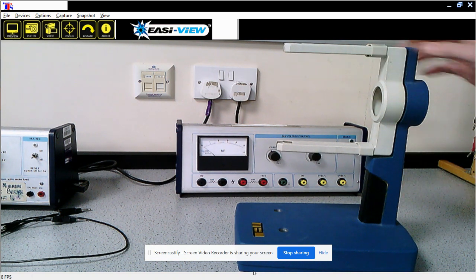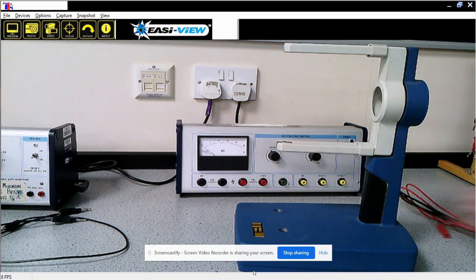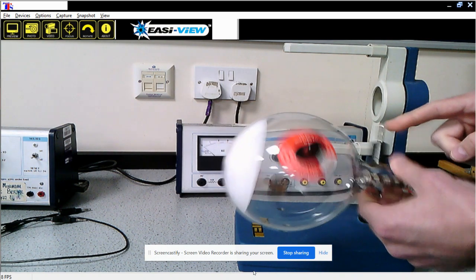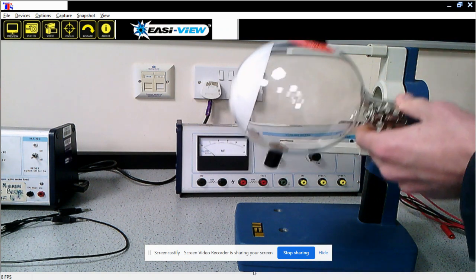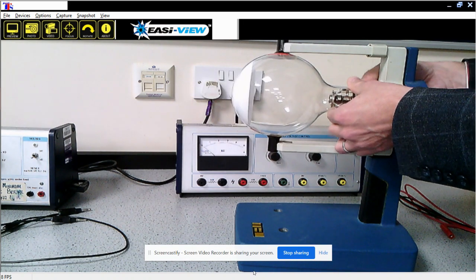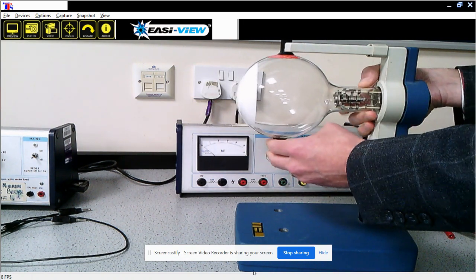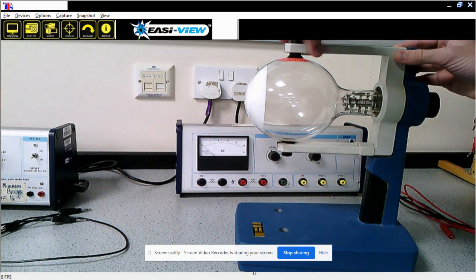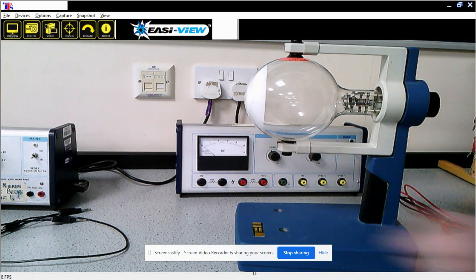When I'm putting the tube in, I'm going to check that these sliding plastic sections are slid to the right, because they will tighten up and grip the beam tube as you move them to the left. So I'm going to have this set up so that this connection is pointing away from me, because that's going to be the anode and that's going to be at high potential. So I'm going to have that pointed away from me, away from anyone walking past. So this just slots in and it will click at the top and bottom. And then to tighten it, I just slide these plastic sections back down and they will grip it.